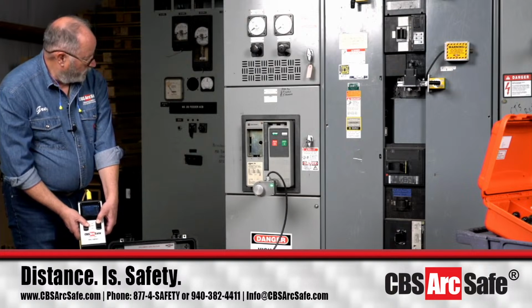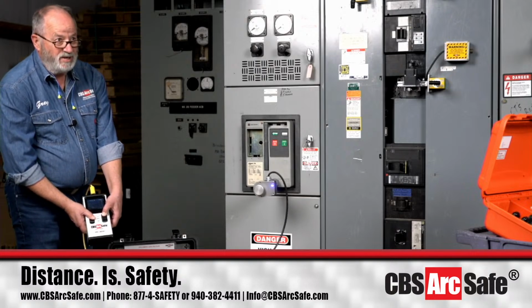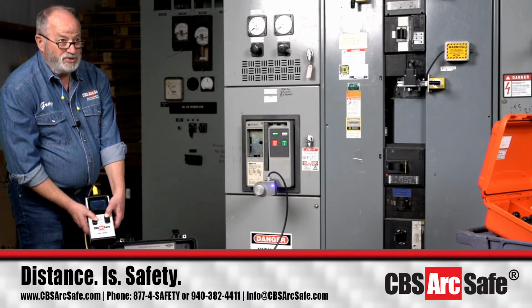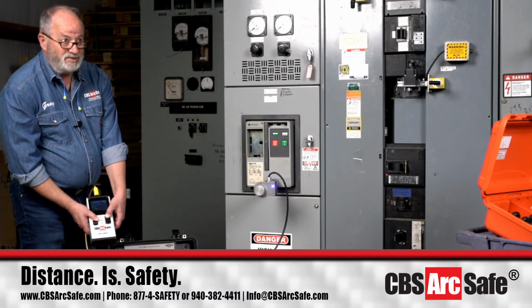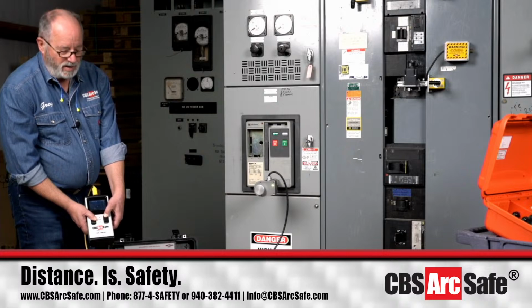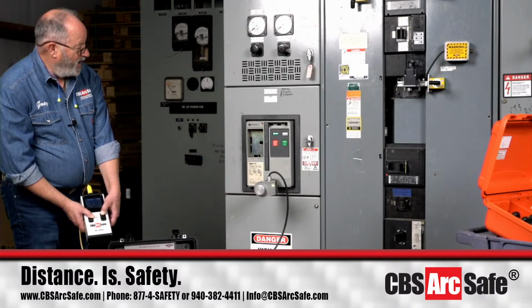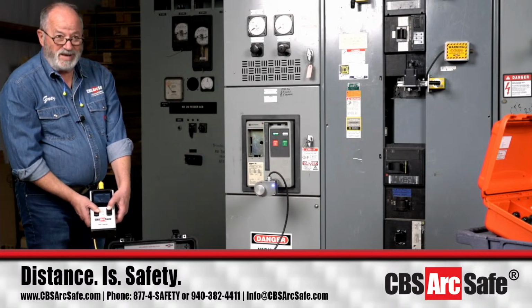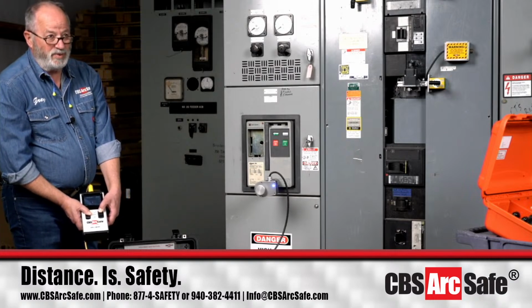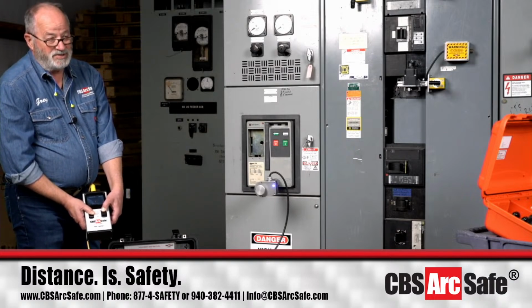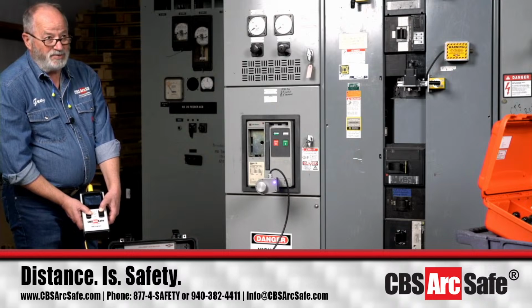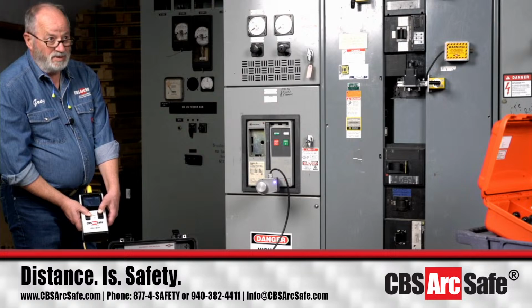One of the things is we've seen some of our competition have problems getting the 5,000 amp breaker in. The Magnum DS breaker, domestically in the United States, the largest one I've seen is 5,000 amps. But the IEC rated breaker is rated up to 6,300 amps, so this will do both of those breakers.